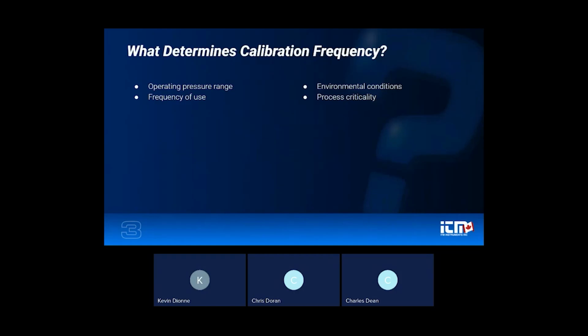So what actually determines this risk? I just spoke about it a little bit, but the biggest one that I typically speak with customers about is the operating range. Instruments that regularly run near the top of their range tend to experience more stress and may require more frequent calibration. Frequency of use plays a major role as well. Pretty obvious, but if a gauge is used daily, it's going to require different recalibration needs than a gauge that's used occasionally. Environmental conditions matter as well.